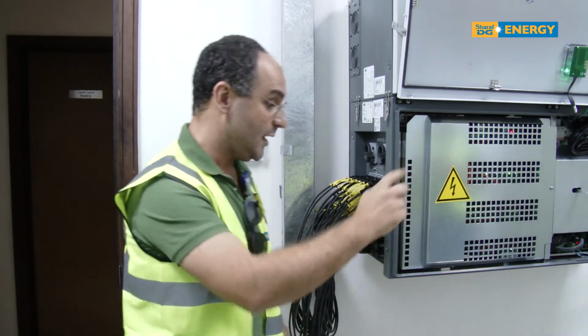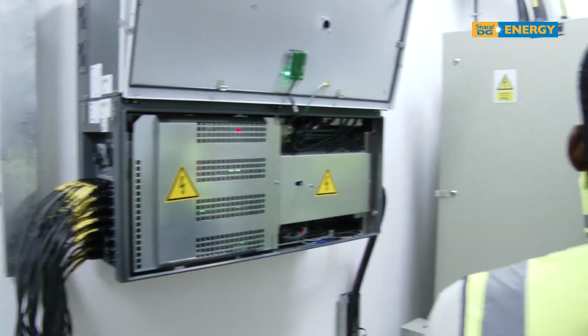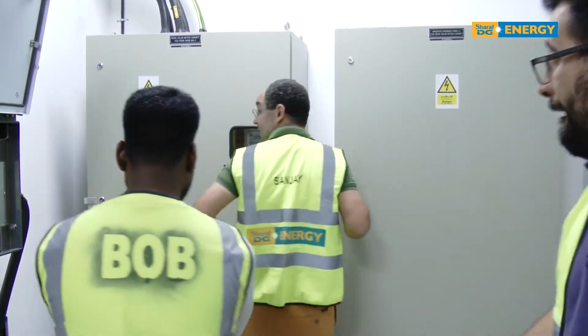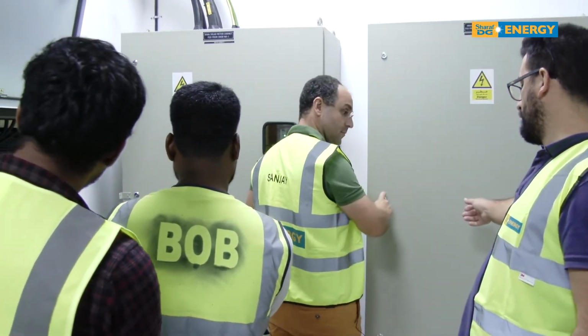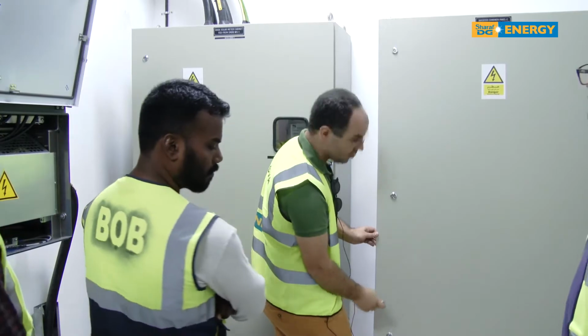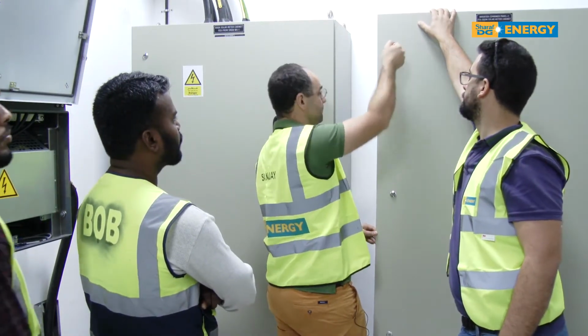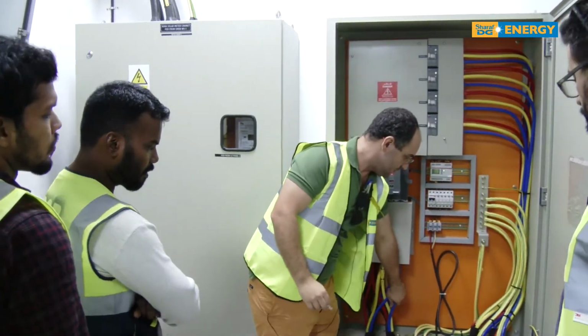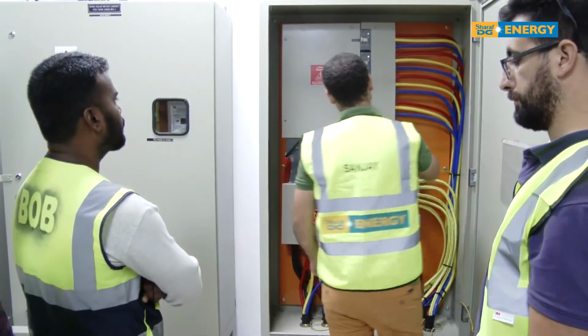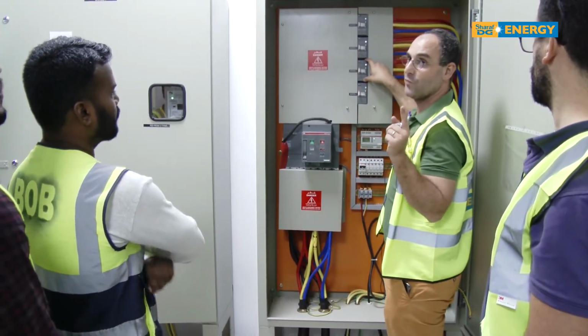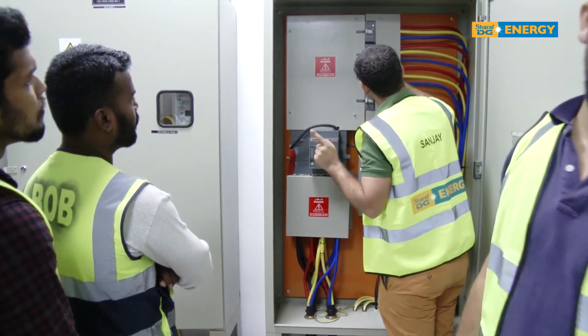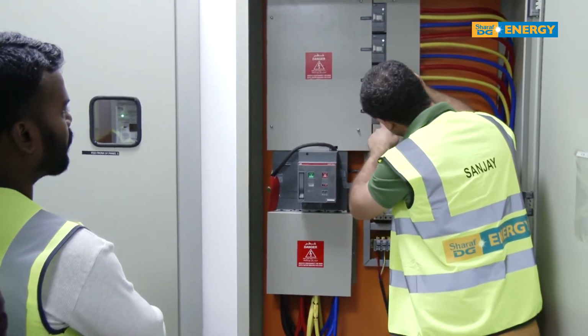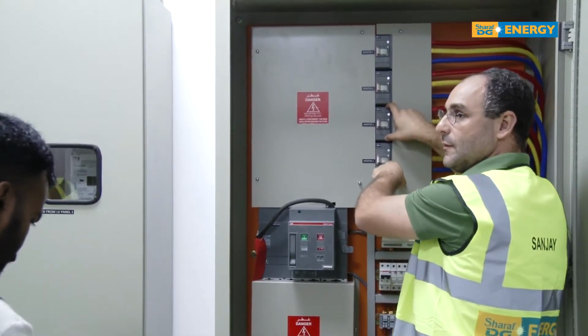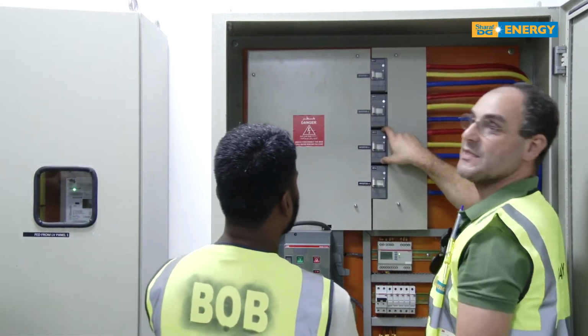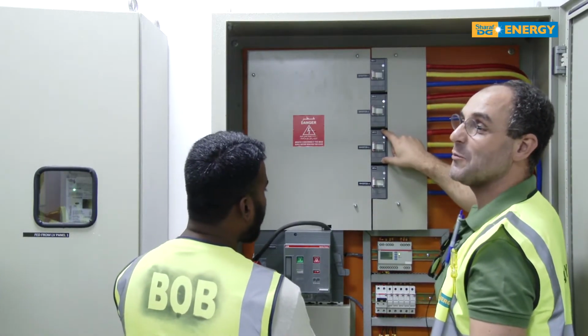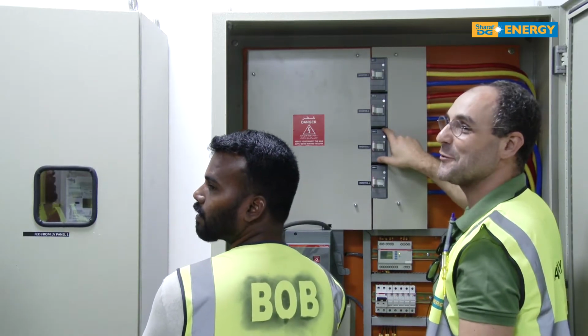Okay, guys? Finally, I want to show you this one. The IGBTs I cannot show you now, but they are inside this machine, okay? Okay, so each breaker is for each one of these machines, all right? And you remember that you have 100 kilowatts, and this breaker is, which size of breaker is it? 200 amps. So we make 150 amps here. We size our breaker for, sorry, I was seeing some red lights. Red lights usually are not good, but these ones are good.